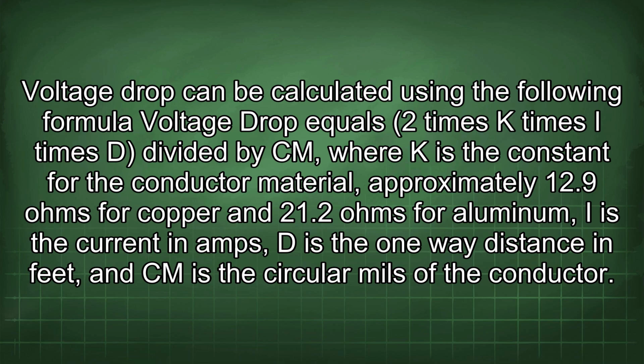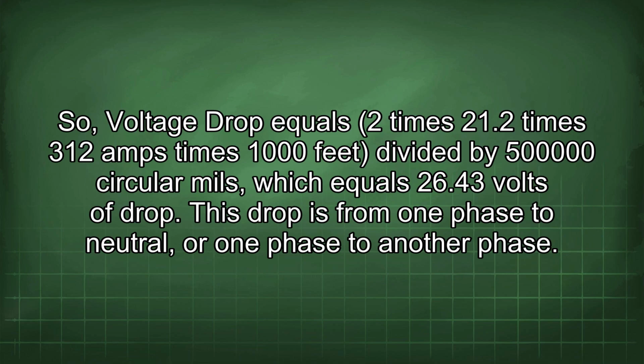of the conductor. So, voltage drop equals 2 times 21.2 times 312 amps times 1000 feet divided by 500,000 circular mils, which equals 26.43 volts of drop. This drop is from one phase to neutral, or one phase to another phase.